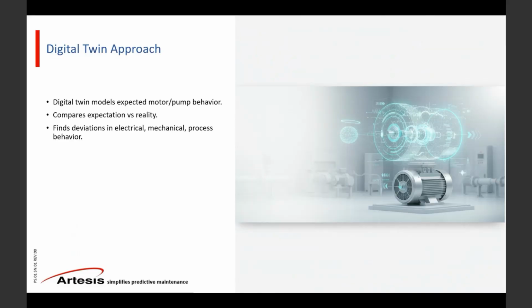And so now, of course, the digital twin approach, which is the second layer, is pretty simple because it's all about expectation versus reality. So you build a model of how a motor, a pump, or a fan, or whatever it is that you're monitoring should behave under normal conditions, and then you continuously compare that expected behavior to what you are actually seeing in the real world.